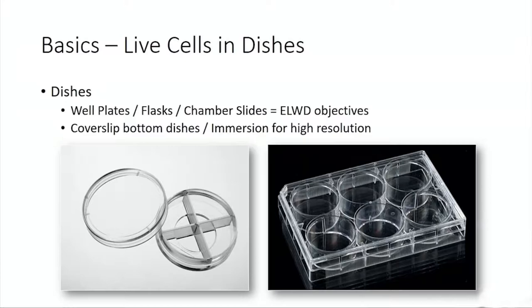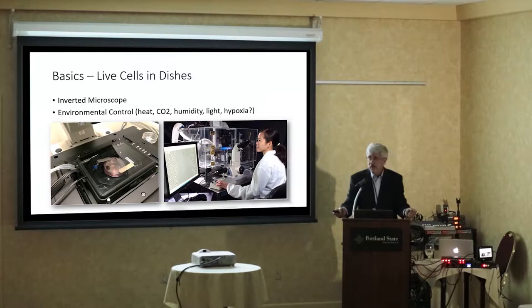So if somebody designs their entire experiment, brings me cells in dishes, and says they want to use 63X on the confocal, and it's a plastic bottom dish — we can't do it. 'But I just spent two weeks growing those cells.' Well, you're going to have to go back and grow them for two more weeks. It would be good to talk to me at the beginning of the process. If we've got live cells, we need to keep them alive and happy — so you're dealing with environmental controls.